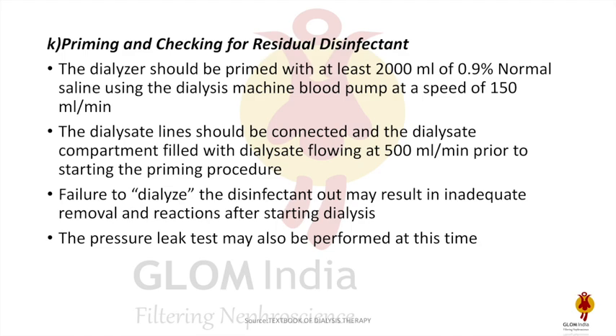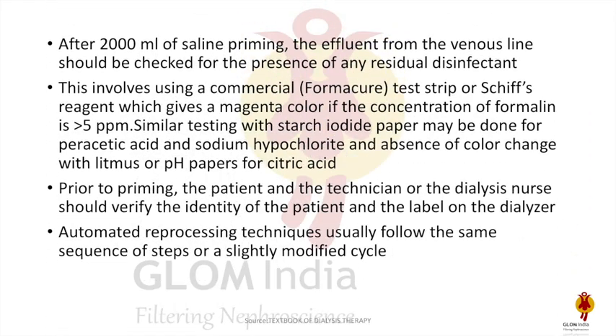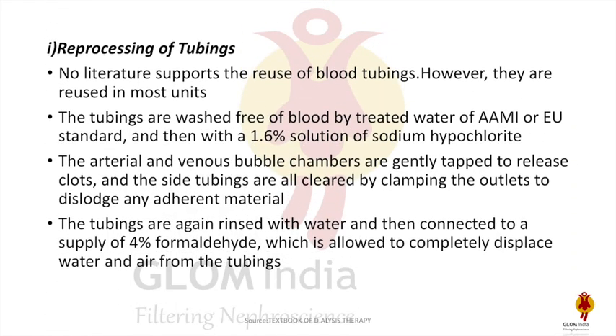A pressure leak test may also be performed at this time. After 2000 ml of saline priming, the effluent from the venous line should be checked for residual disinfectant using commercial test strips or Schiff's reagent, which gives a magenta color if the concentration of formalin is more than 5 ppm. Similar testing with starch iodide paper may be done for peracetic acid and sodium hypochlorite, and absence of color changes with litmus or pH paper for citric acid. Prior to priming, the technician or dialysis nurse should verify the identity of the patient and the label of the dialyzer.